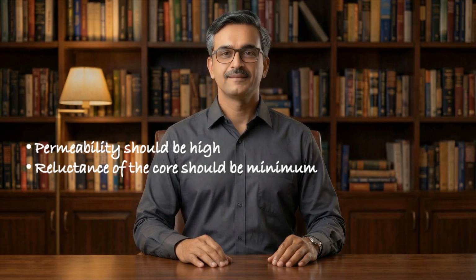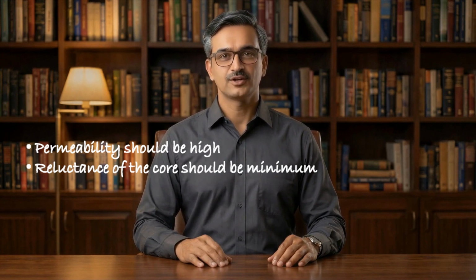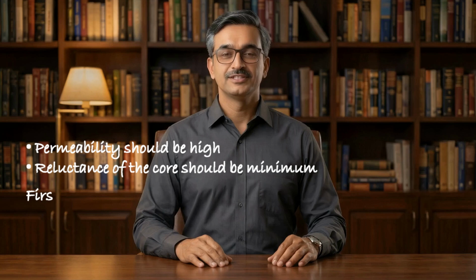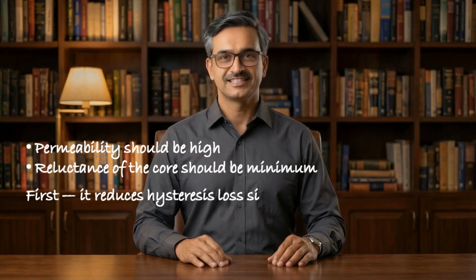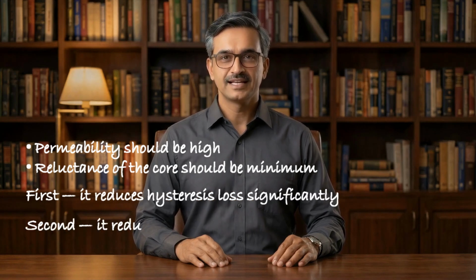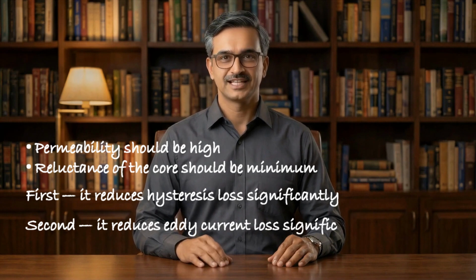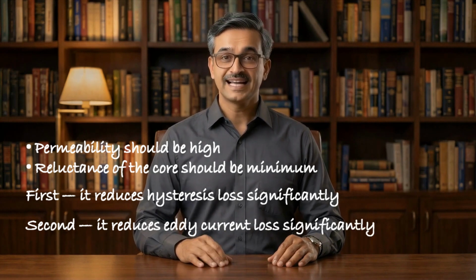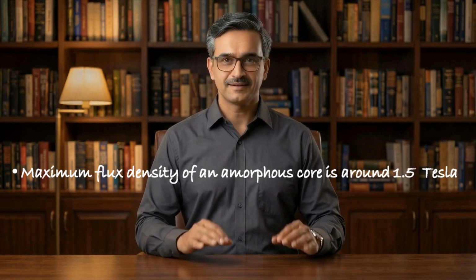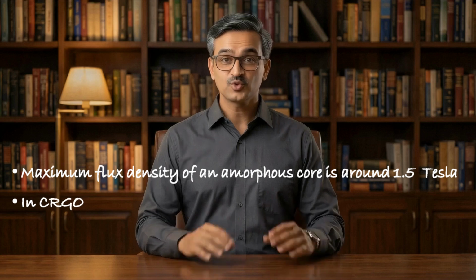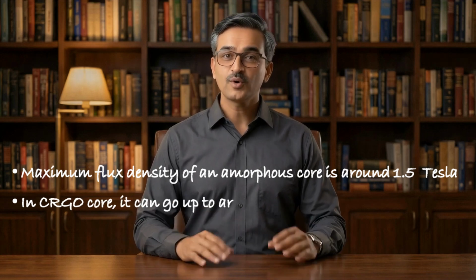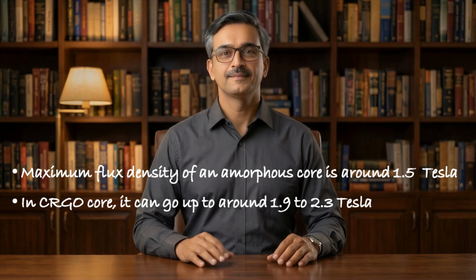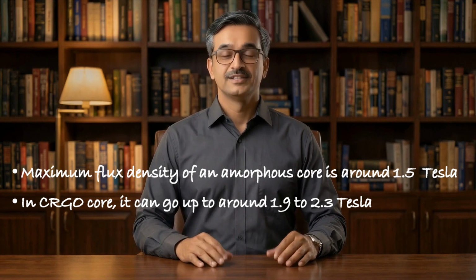Now listen carefully. In an amorphous core, there are two main advantages. First, it reduces hysteresis loss significantly. Second, it reduces eddy current loss significantly. But in terms of flux carrying capability, amorphous cores show inferior performance. The maximum flux density of an amorphous core is around 1.5 Tesla, whereas in a CRGO core, it can go up to around 1.9 to 2.3 Tesla. Now let us understand why this occurs.